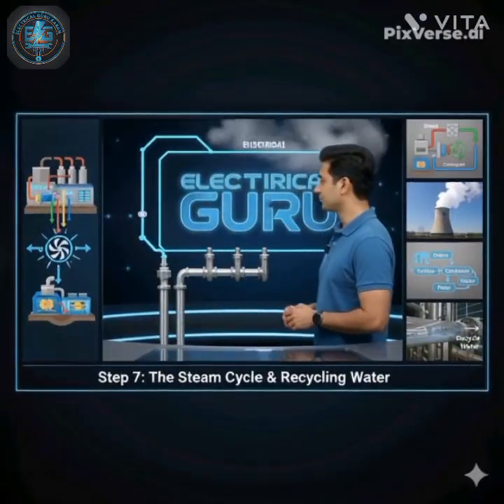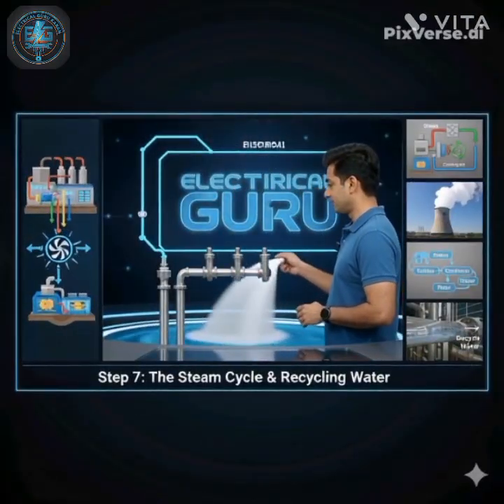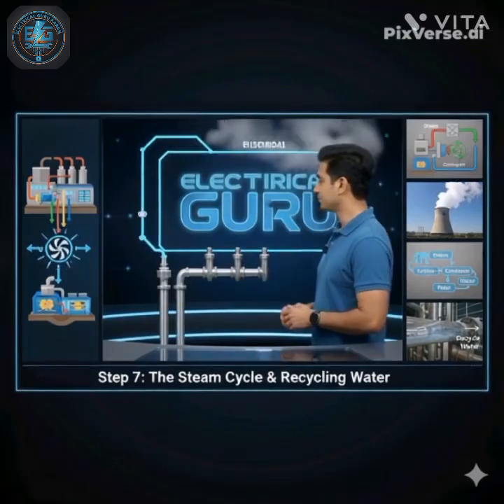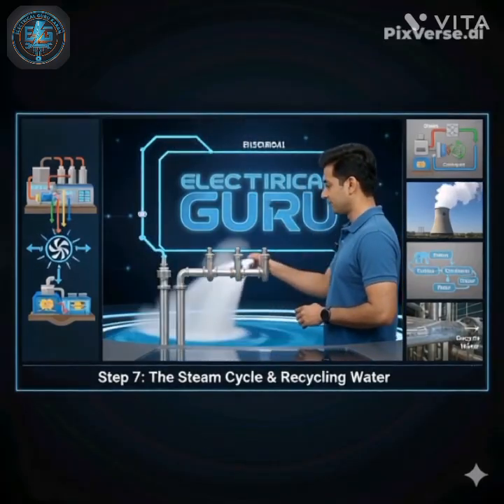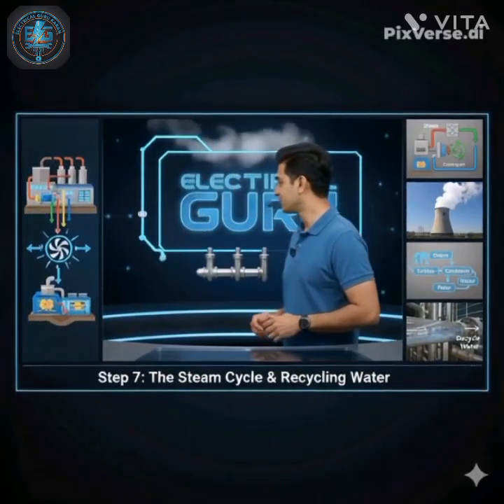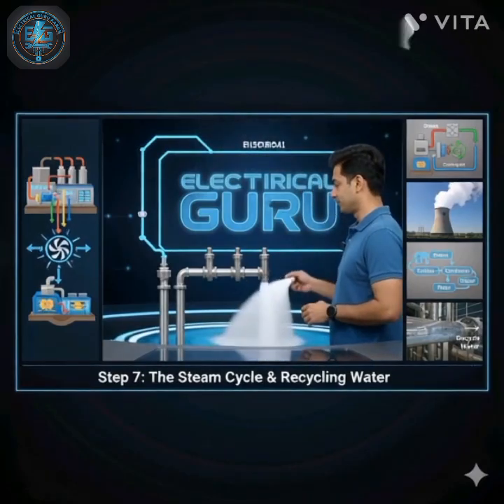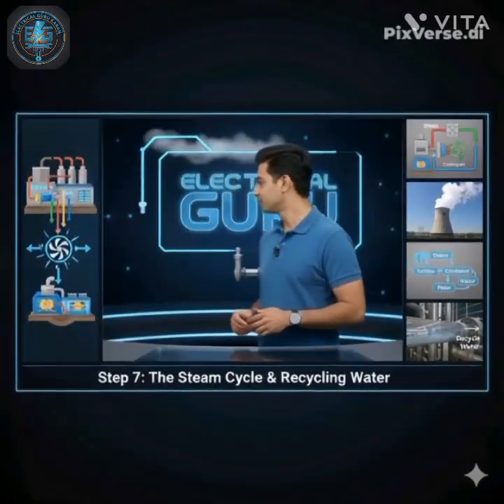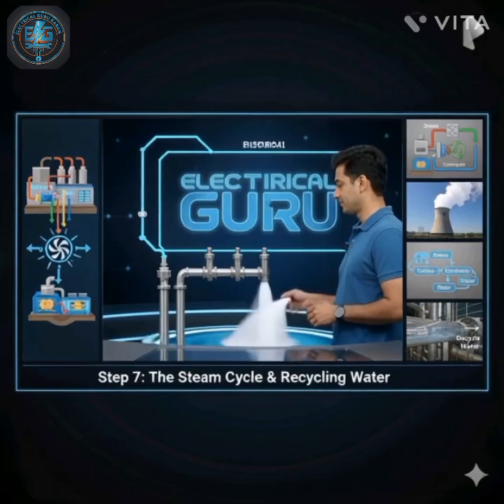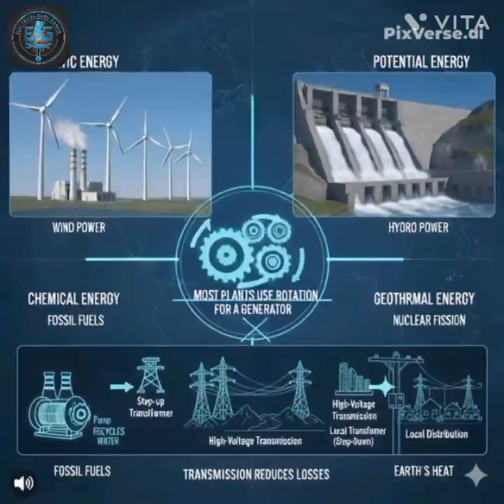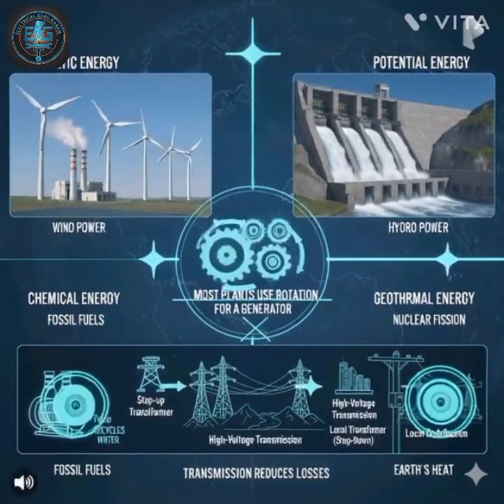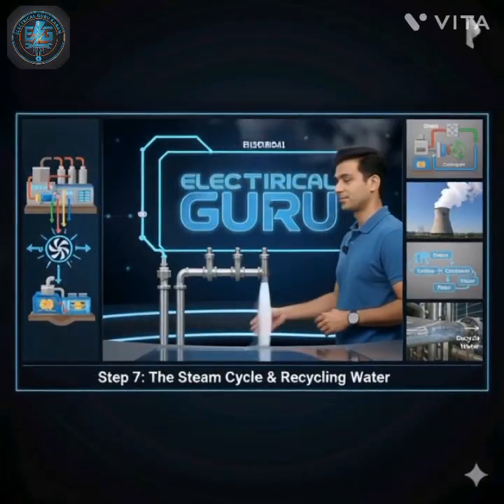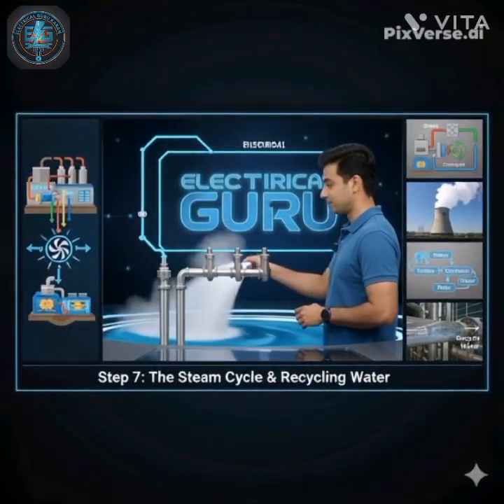Step 7. The steam cycle and recycling water. In steam plants, the process is usually a closed loop. After steam passes through the turbine and expands, it enters a condenser where it cools and turns back into water. Pumps return this condensate to the boiler. Recycling water conserves resources and keeps the plant running continuously.